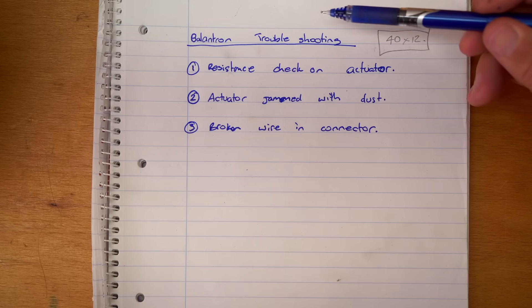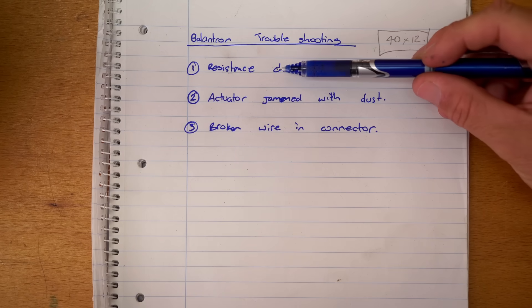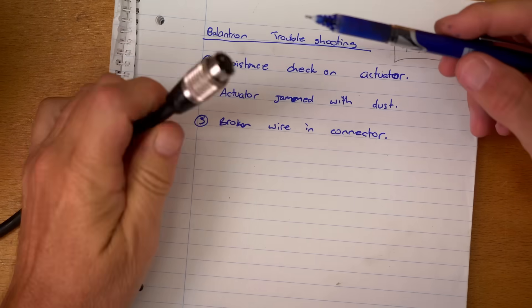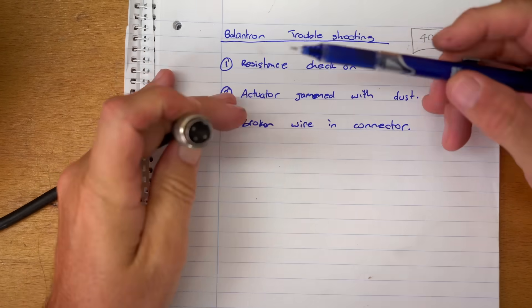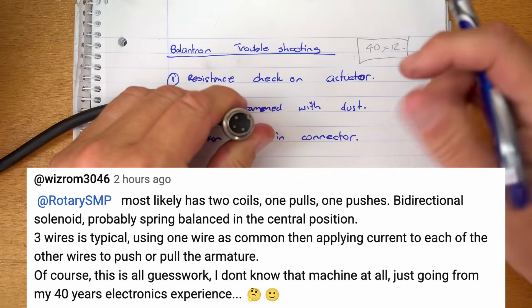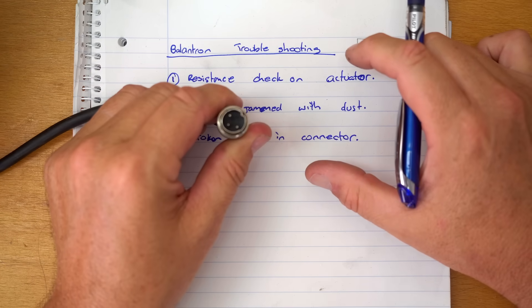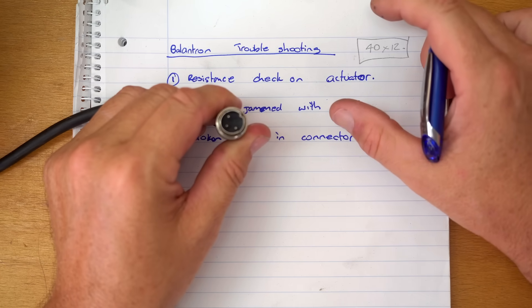Now running through some of the excellent troubleshooting advice, the first one and most obvious is to do a resistance check on this actuator. I think most people think it's probably a solenoid and because there's a three pin connector it's probably a double solenoid with one coil for extend and another coil for retract.